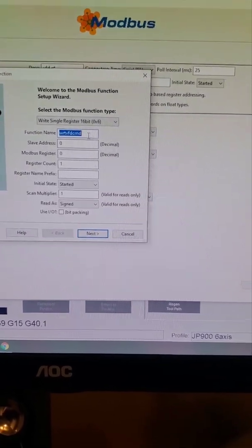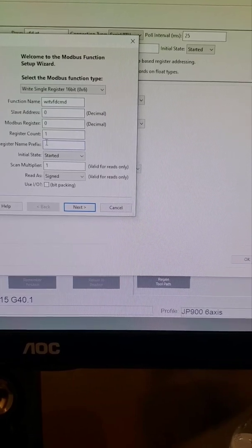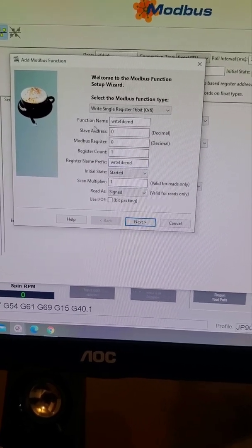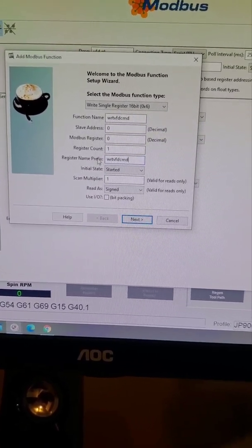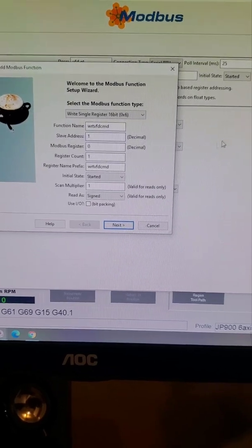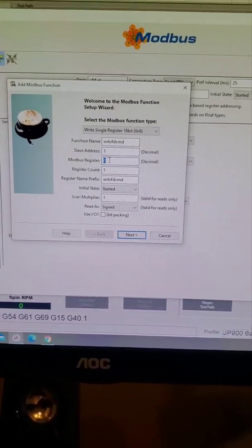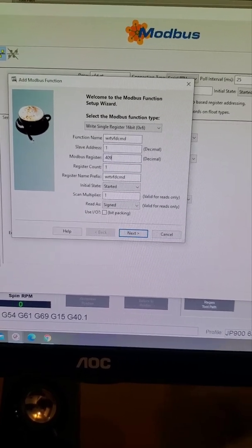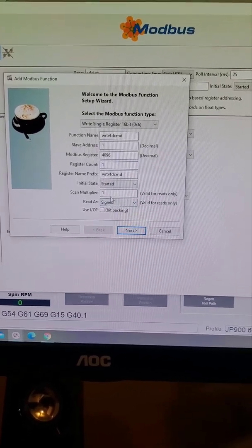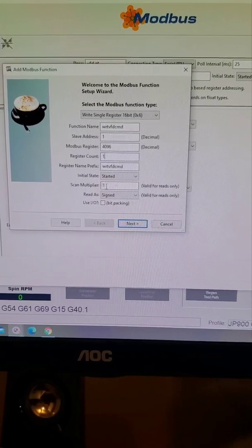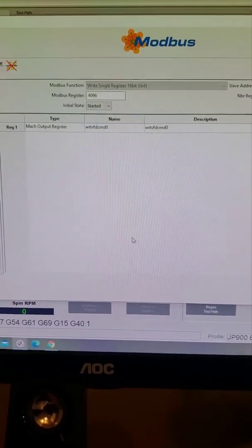Okay, copy and paste over here, and you can copy and paste down here. The functions name and the registers name prefix are the same. Slave address 1 and Modbus address is what the manual says, 4096. Okay, and you can keep all these default. Next, verify, finish.